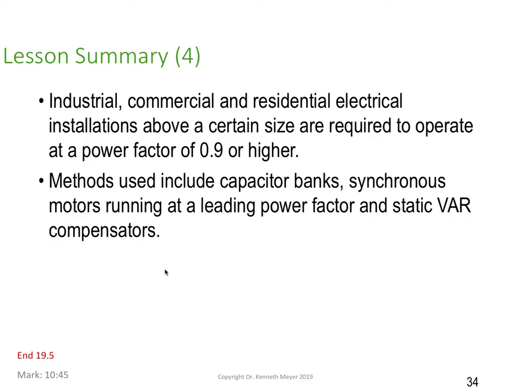And finally for this lesson, industrial and commercial and residential installations above a certain size. So if you've got residential above 10 units, then you have to maintain a power factor of 0.9 or higher. If you fail to do so, then the supply authorities are going to charge you a lot of money for that kVA demand charge.